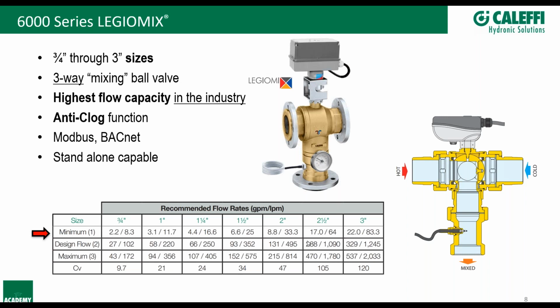So within the control, there really isn't going to be any secondary protection. With the scheduling function, you're picking specific days, specific times of the day and specific durations. The idea is that even if your storage tank ramps up and doesn't come back down for whatever reason, the mixing valve should still be able to control that back down to whatever your distribution temperature needs to be. So even if you ramp that tank up to 180 and do your thermal disinfection at 160, after that duration is done, it's going to come back down to your normal setpoint.